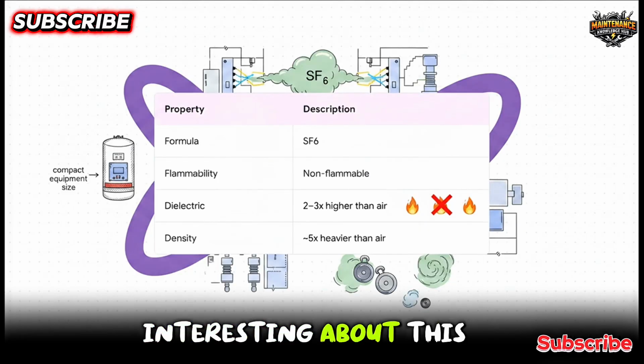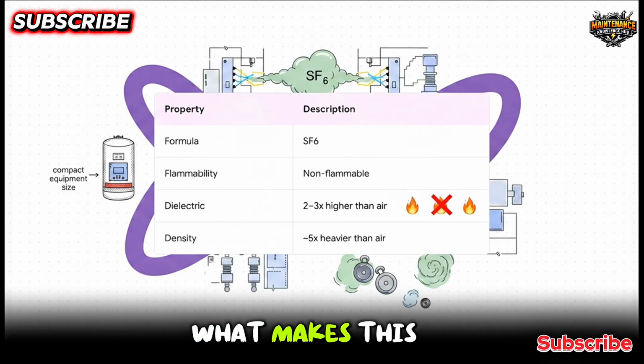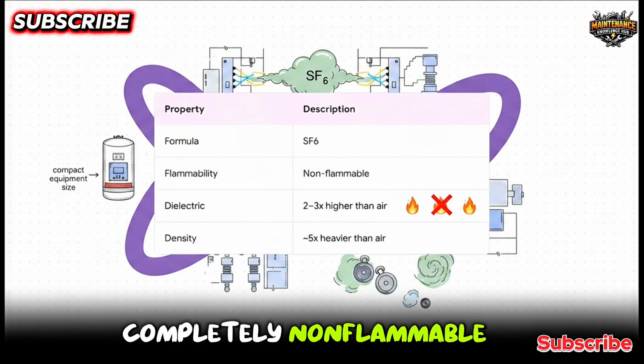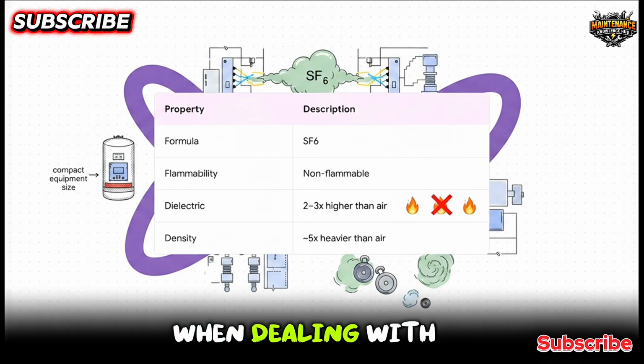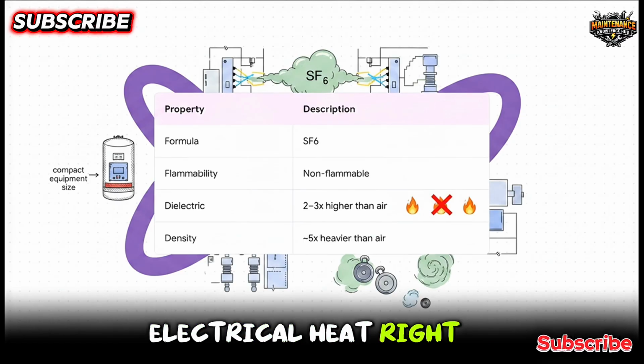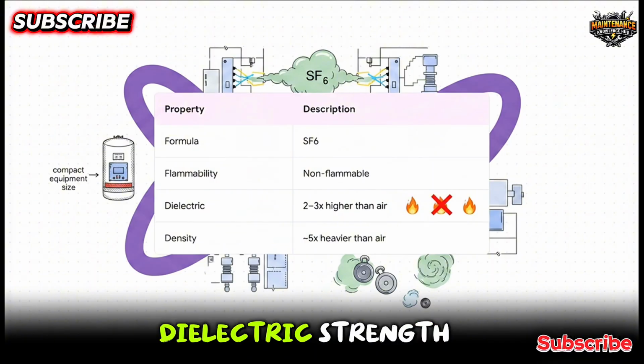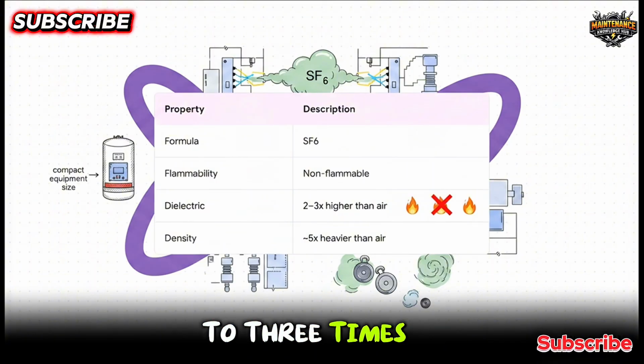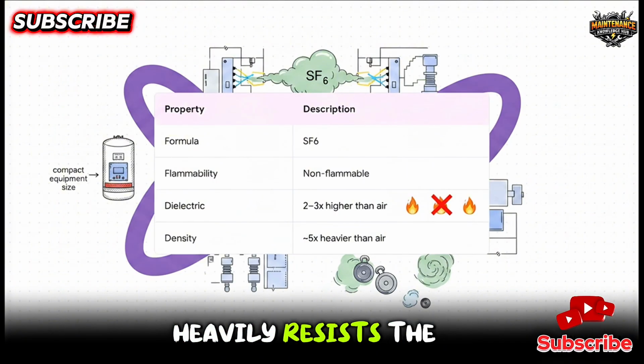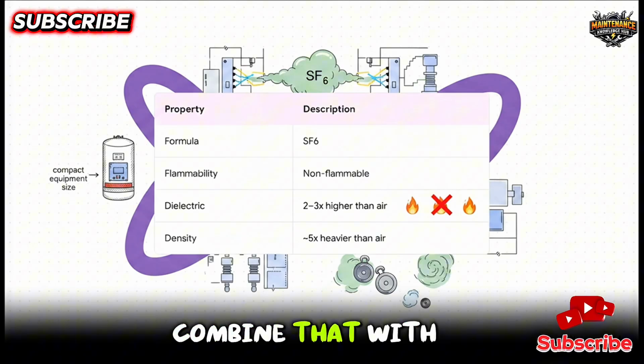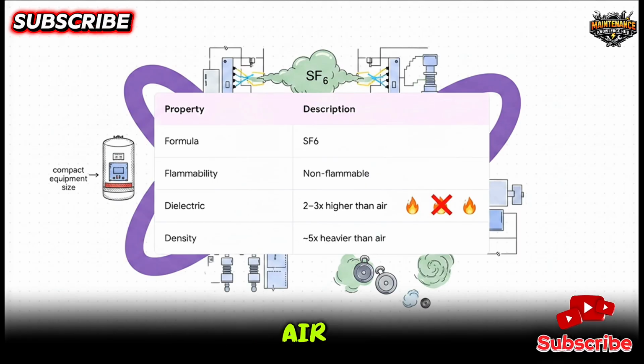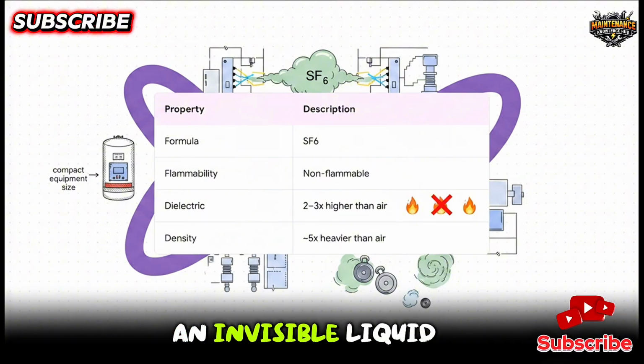Now, what's really interesting about this is why SF₆? What makes this gas so miraculous compared to just the standard air we breathe every day? Well, first off, SF₆ is completely non-flammable. That is exactly what you want when dealing with explosive electrical heat, right? But its real superpower is its dielectric strength. It's actually 2 to 3 times higher than regular air, meaning it heavily resists the flow of electricity. Combine that with a density that's roughly 5 times heavier than air, so it literally pours almost like an invisible liquid, and you've got a medium that packs incredible insulating power into a really compact space.